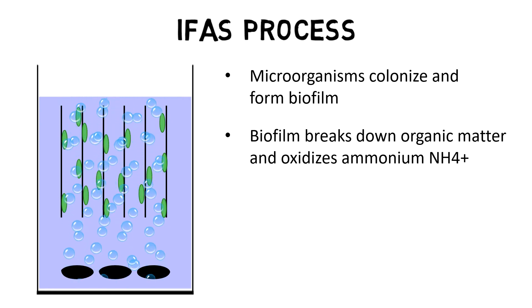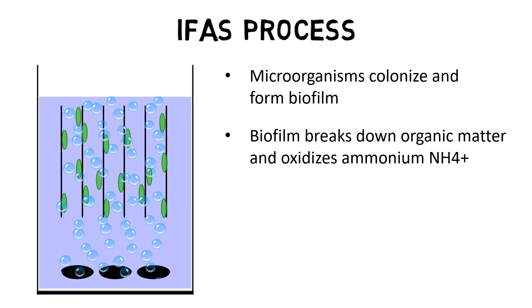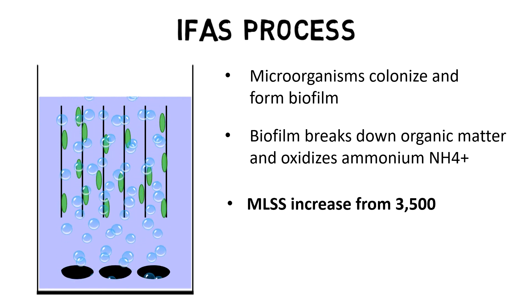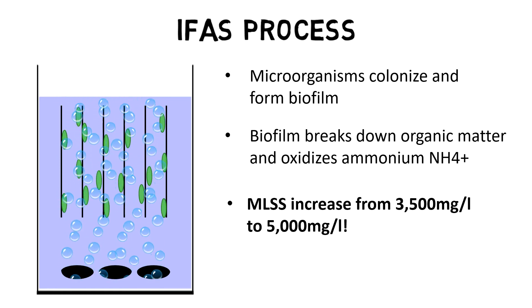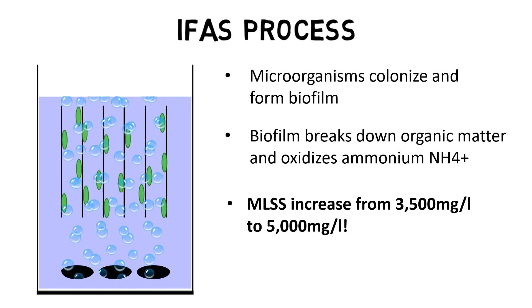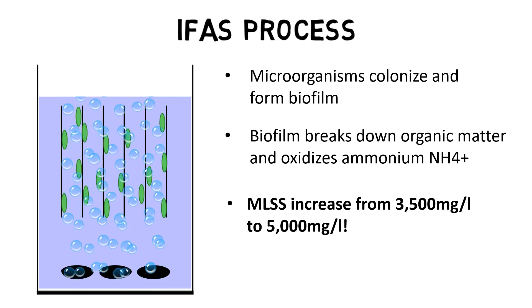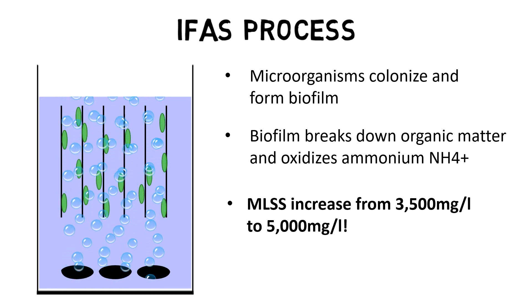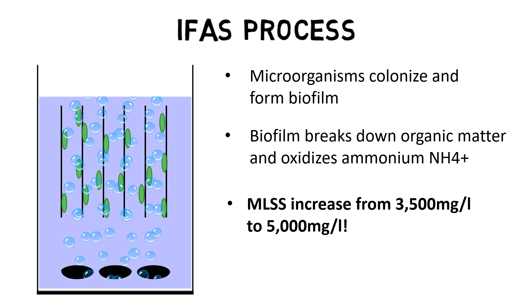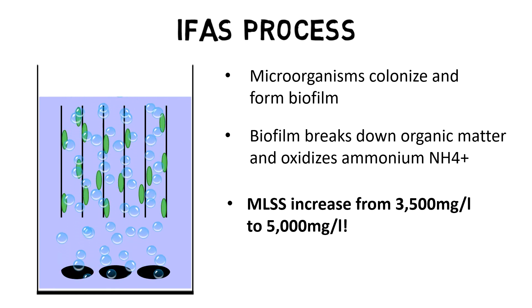Compared to conventional activated sludge systems, the MLSS can be increased from 3,500 milligrams per liter up to 5,000 milligrams per liter, which equals a capacity increase of about 50 percent.